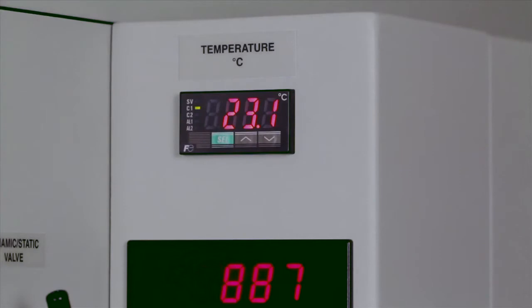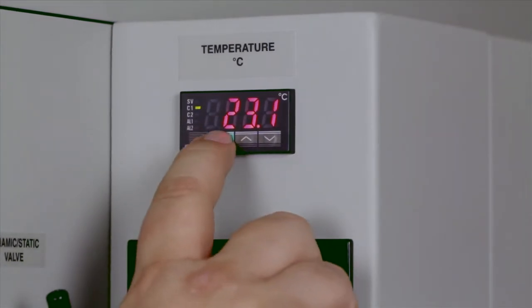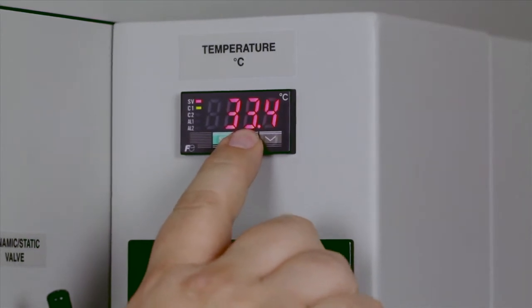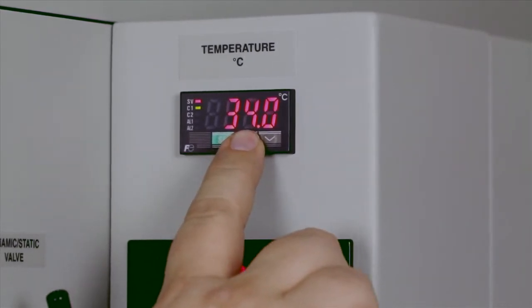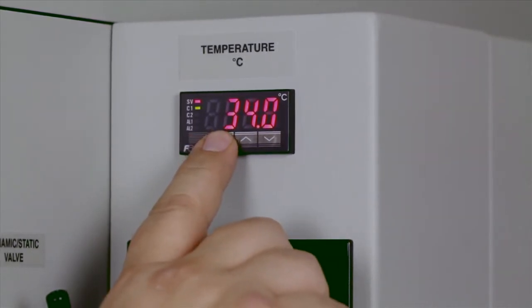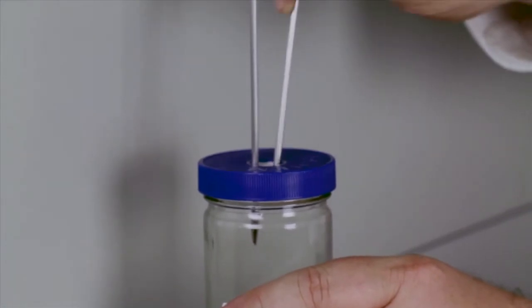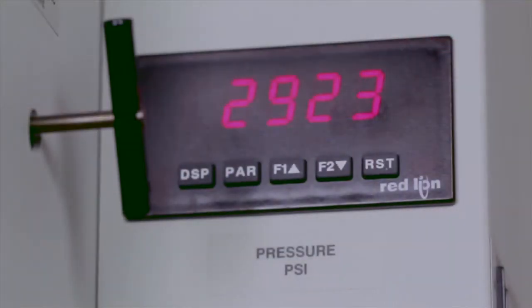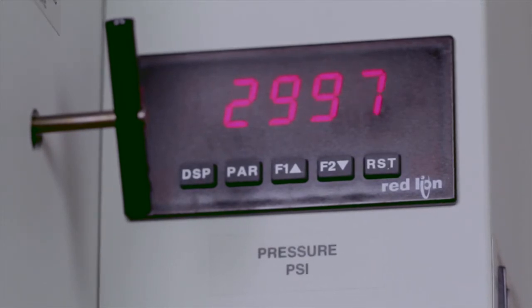Set the temperature for the experiment. Locate the LED labeled temperature. Press the set button, then the up or down arrow to adjust temperature, then press the set button again. Place a collection jar with a vent tube in the collection assembly area and connect the outlet to the flow meter or vent.